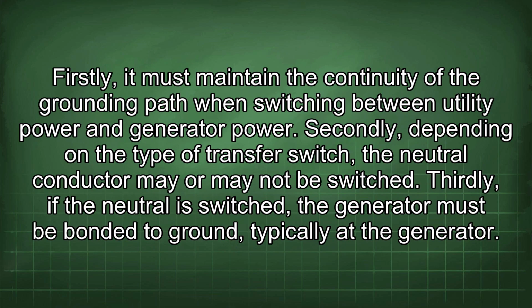Firstly, it must maintain the continuity of the grounding path when switching between utility power and generator power. Secondly, depending on the type of transfer switch, the neutral conductor may or may not be switched. Thirdly, if the neutral is switched, the generator must be bonded to ground, typically at the generator.